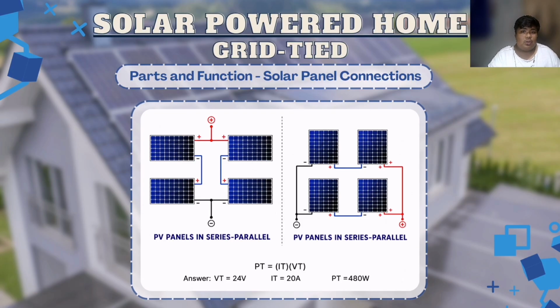In this example, we are going to use 4 panels, each 12 volts and 10 amps. We wired two pairs in series to create two sets of 24 volts and 10 amps, then wired the two sets in parallel. In the end, our total rated output for the four panels in this combination connection is 24 volts and 20 amperes. Using our formula, 20 amps times 24 volts, the total power output is 480 watts. This is higher than our previous example because we increased the panel count to 4. And if we use 4 panels in a pure series or pure parallel setup, the result will still be 480 watts. Understanding this basic photovoltaic connection is vital for us engineers — it allows us to adjust rated output specifically to the needs of the system we are designing.